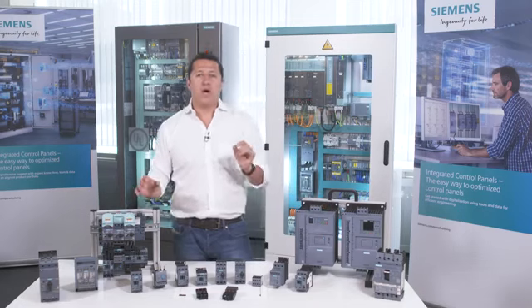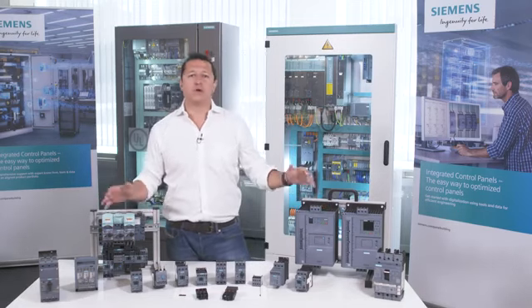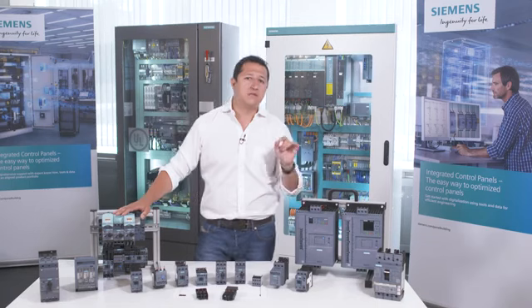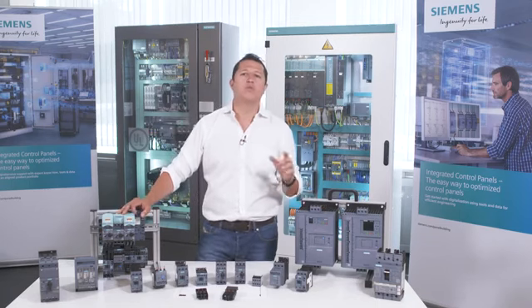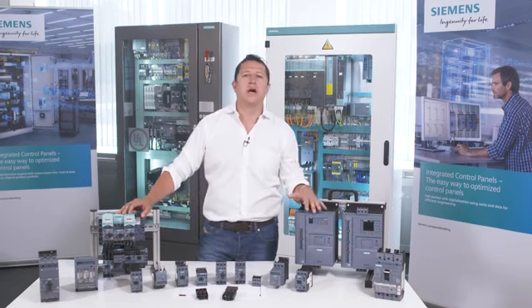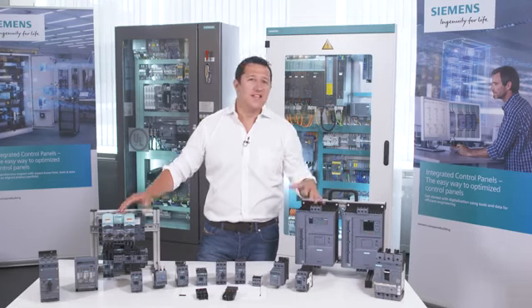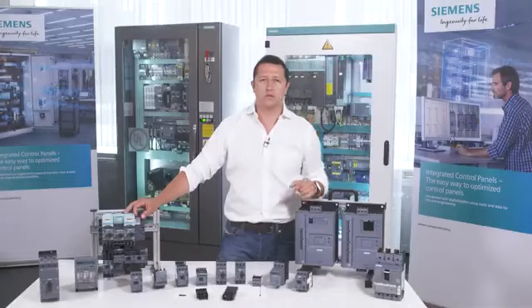As you can see, we have the standardized solution for various markets, but keep in mind that SCCRs will vary according to the product standard that we must comply with at Siemens. This also happens for soft starters and frequency drives. They have been tested under different product standards, but also have tested combinations and have been tested for high-capacity short-circuit current ratings.